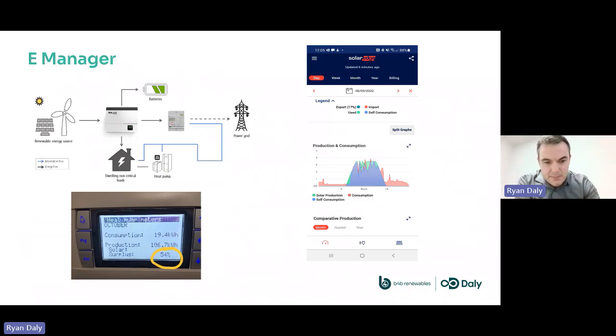And you can see in the stat on the bottom left that in the month of October, 54% of our production was generated with the excess mode or surplus mode, which cuts down obviously a lot on the cost of running the heat pump. The graph on the right then shows your solar kicking in, which is the green, and then the blue is more or less the heat pump mimicking what the solar is giving it. So we'll actually manage the revs per minute of the compressor to match exactly what the PV is giving it, and it works really well.